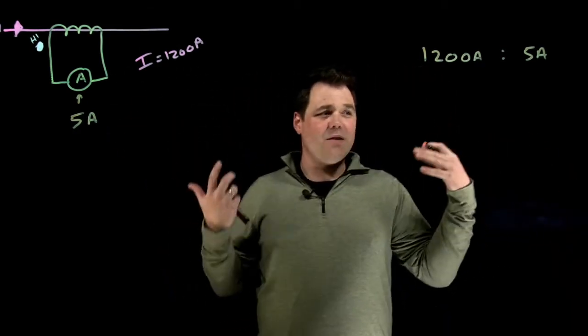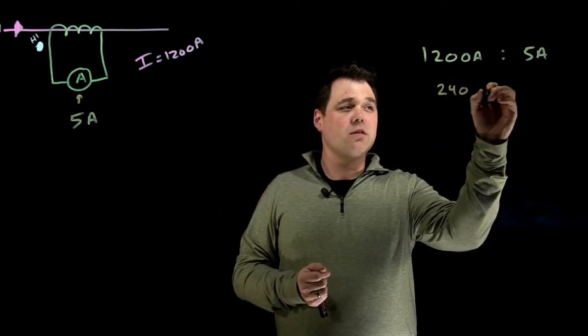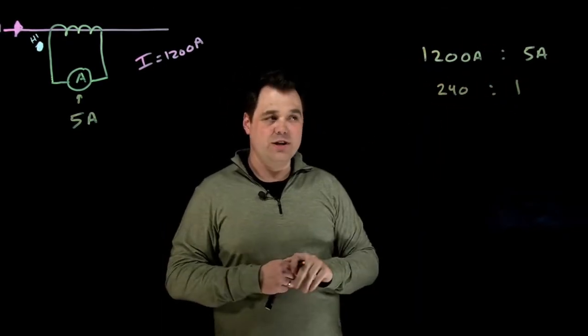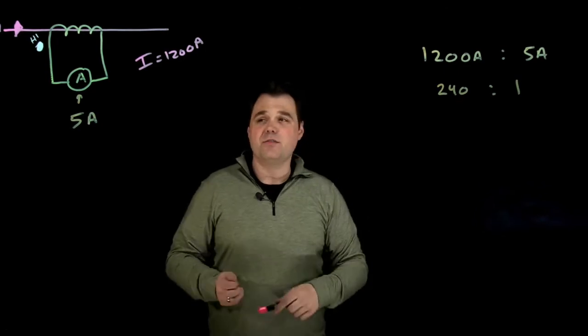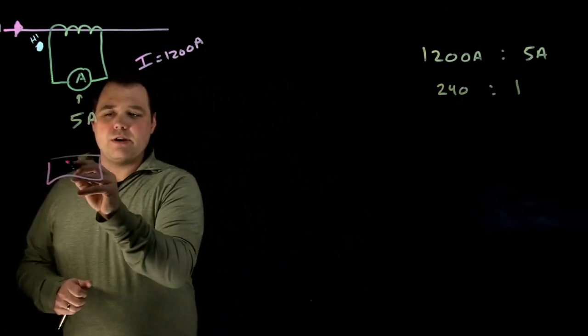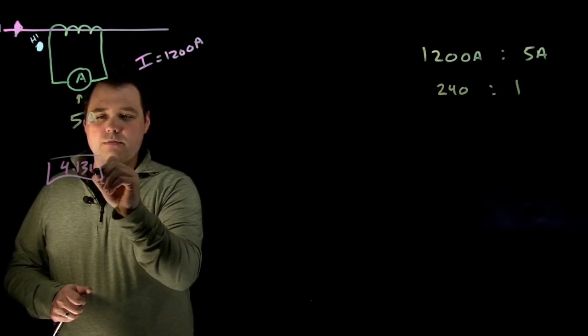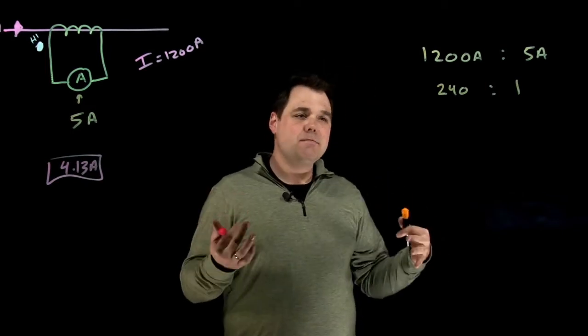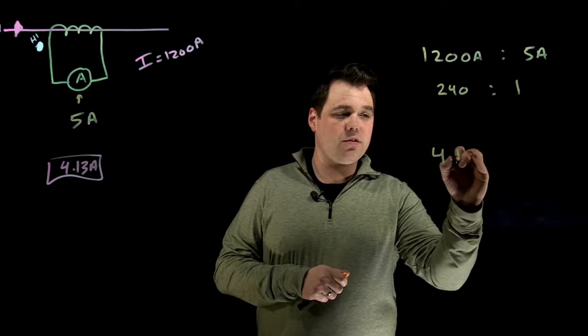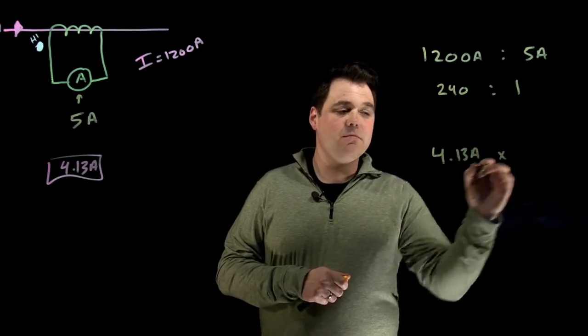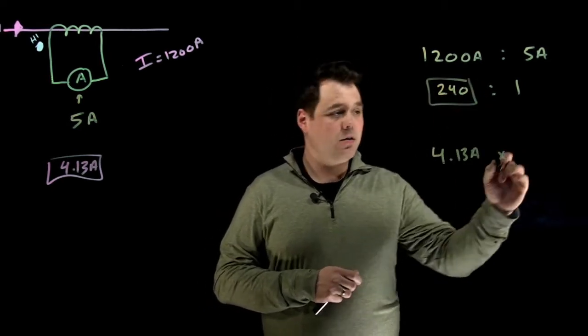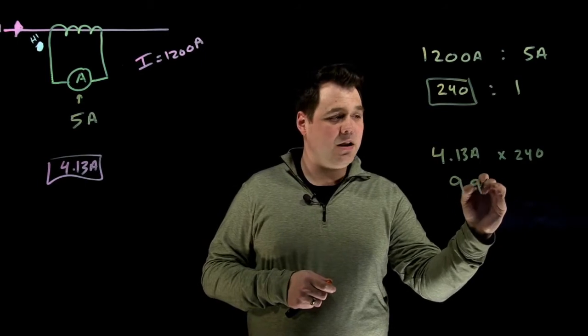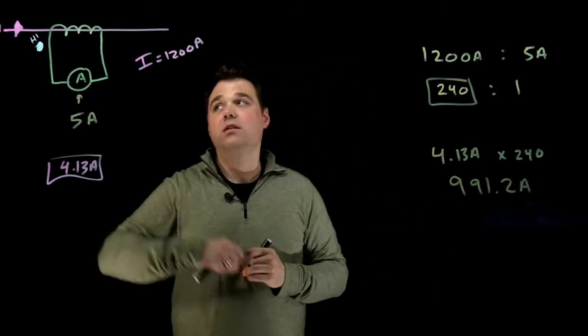Now, that would be if we do break down the math, that's a 240 to one ratio. I just took 1200 divided by five, 240 to one ratio. Now let's just say, hypothetically, for our example here, my ammeter reads 4.13 amps. My ammeter is reading 4.13 amps. Well, what does that mean? Well, I'm going to take that 4.13 amps, and I'm going to multiply it by my ratio by 240. That means in this circuit, there is actually 991.2 amps flowing on the primary.